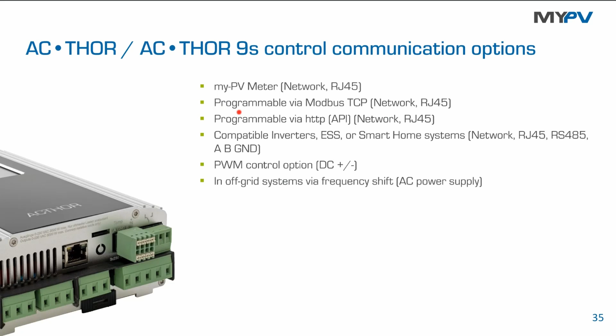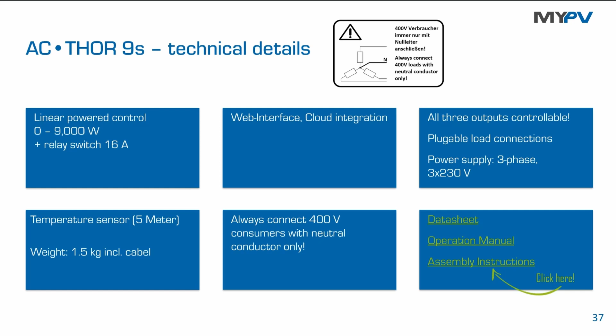When you connect an ohmic load, an electric heating element, to the unit, it needs to have a neutral conductor. The AC Thor 9S is connected in a star connection. It's not working in a delta connection. And due to this neutral conductor, it is able to detect the nominal power of its load automatically. So this also works for the single phase variant. You can also connect 1.5 kilowatt, 2 kilowatt immersion heaters, it does not matter.